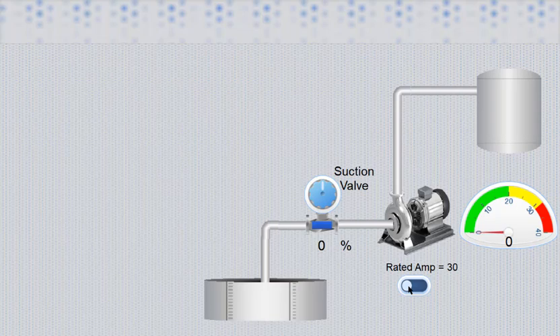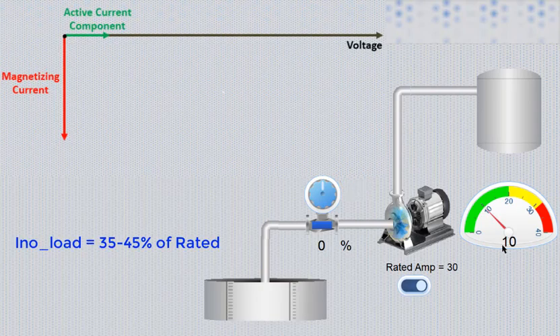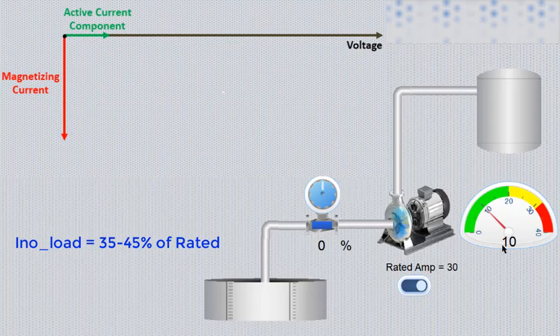When motor is turned on, then it draws 10 amperes current which is no load current. No load current of induction motor is 35 to 45 percent of full load current.